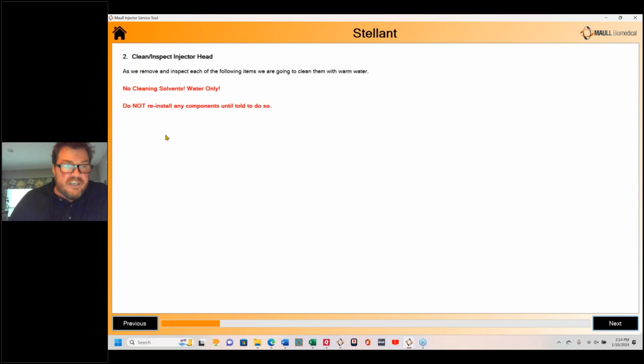Both contrast and saline are water soluble. They might dry. Contrast dries very hard and thick and sticky, but at the end of the day, it is water soluble. So you don't need any special cleaning solvents. You don't need any of those sani wipes you have all over the hospital. Just hot water and a wet rag, hot water and a rag and elbow grease, and that will get all the contrast off. And this screen was just reiterating that.